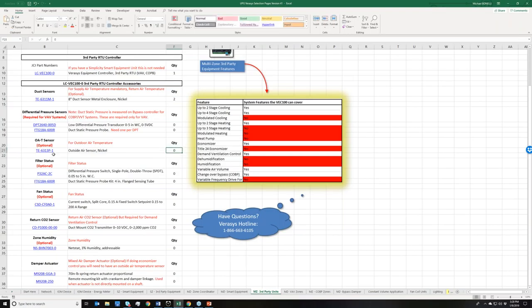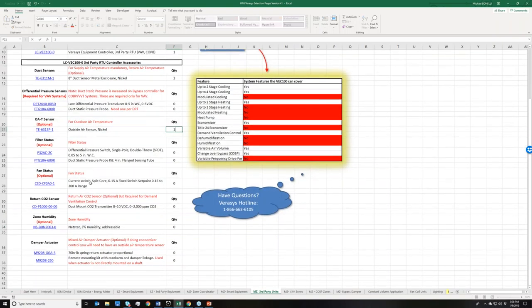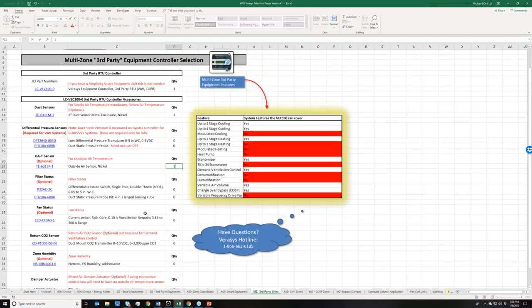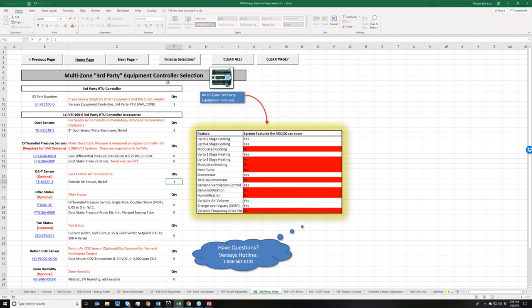Again, given the low cost of these sensors, I always like having outdoor air temperature so I can see it. If I'm going to do demand ventilation control or economizer control, I want to have an outdoor air temperature sensor, so I'm going to throw one of these on there. The rest is up to you whether or not you want to include it. For this purpose, I'm not going to include filter status or fan status, return CO2, or zone humidity. You can absolutely add them to the controller—don't worry about that. We have fixed inputs where you can connect the sensor. That's not a problem, but we're going to move on.